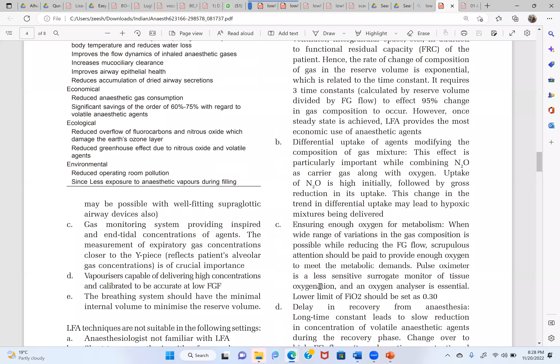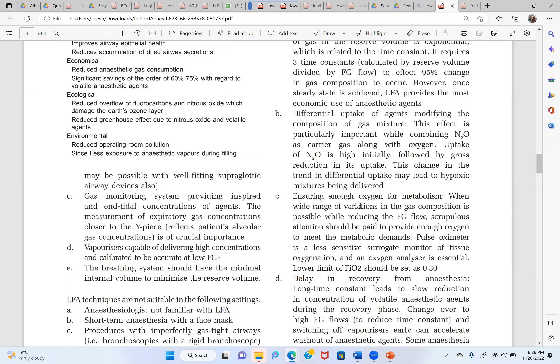Okay. So similarly, differential uptake of agents modifies the composition of the gas mixture. This effect is particularly important while using nitrous oxide as a carrier gas because of its second gas effect. Uptake of nitrous oxide is high initially, followed by a gross reduction in its uptake. This change in the trend of differential uptake may lead to a hypoxic mixture being delivered.